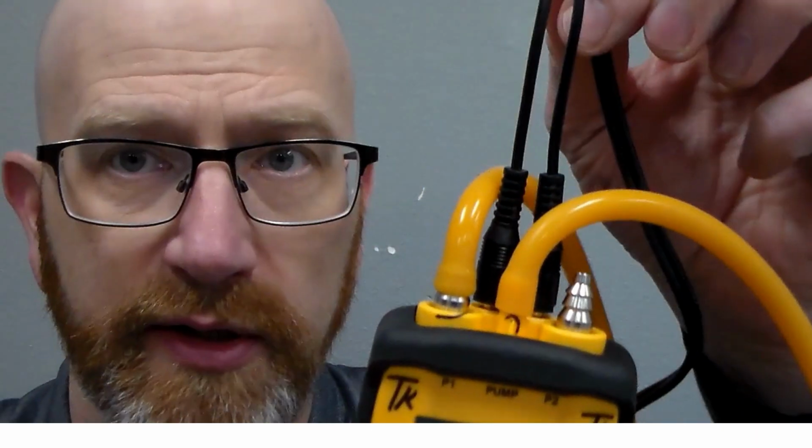What you can do with this is establish a given draft with a little pump inside of here, and then there's an ohm meter that connects to it as well, and this allows you to dial that switch in at a specific inches of water column. Instead of just turning the screw and guessing, this gives you a much more precise way of setting up an adjustable pressure switch. Who knows, perhaps we'll do a video on that sometime. All right, so now that we've got our switch, let's go ahead and get this unit reassembled and get it back on the road again.